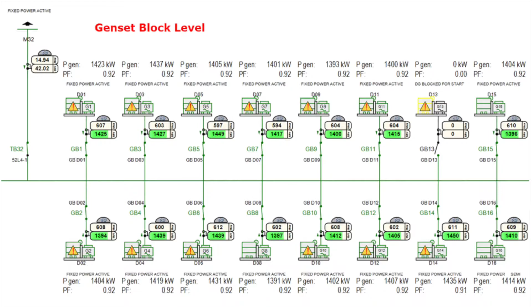This is just jumping down into one group of gensets. Right here, everything's running at about 0.92, 0.91 power factor. But this is all being done fully automatically in the power plant. So I go to my master control system. I want 300 meg. I want you to run at 0.92 power factor. Start. No operators running around starting and stopping engines. That's the SCADA part, supervisory control. So I'm supervising it, I'm controlling it, I'm telling it what to do, and then I'm monitoring it in real time.